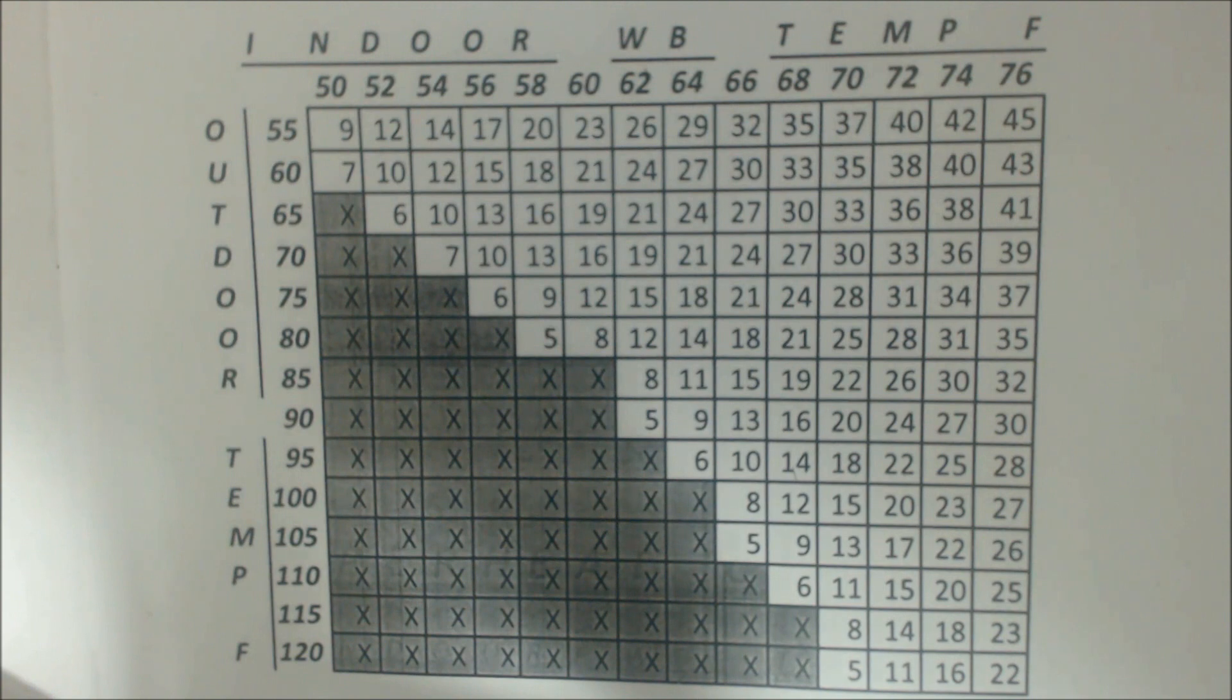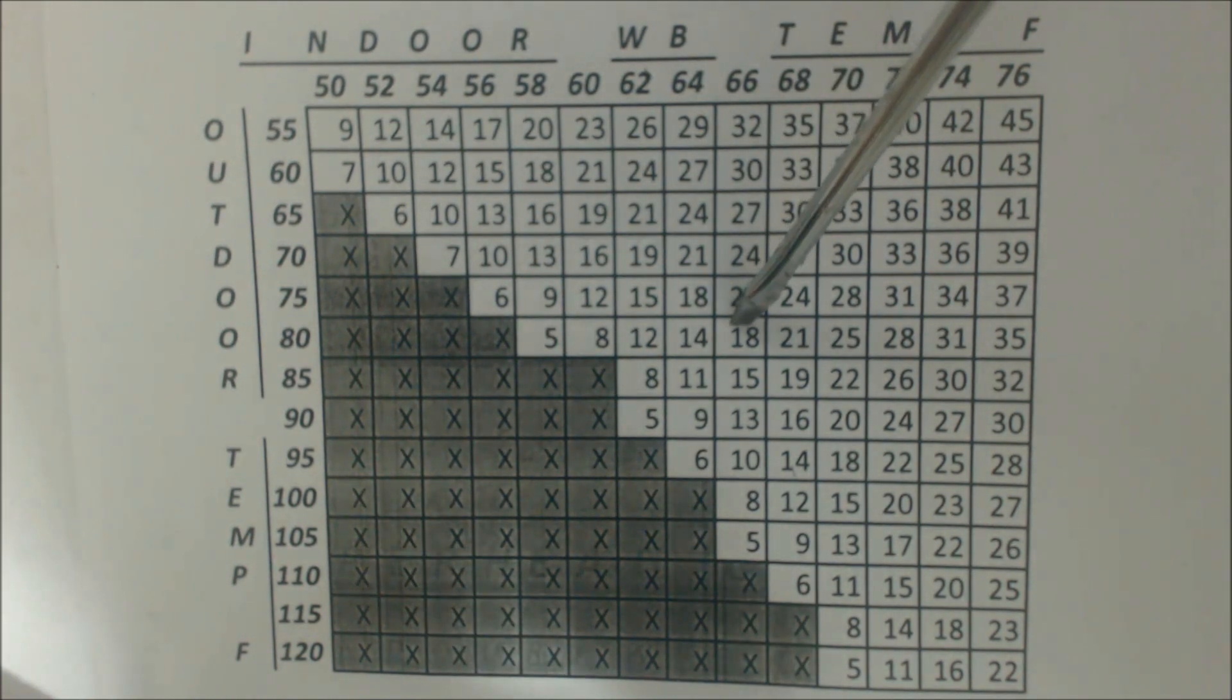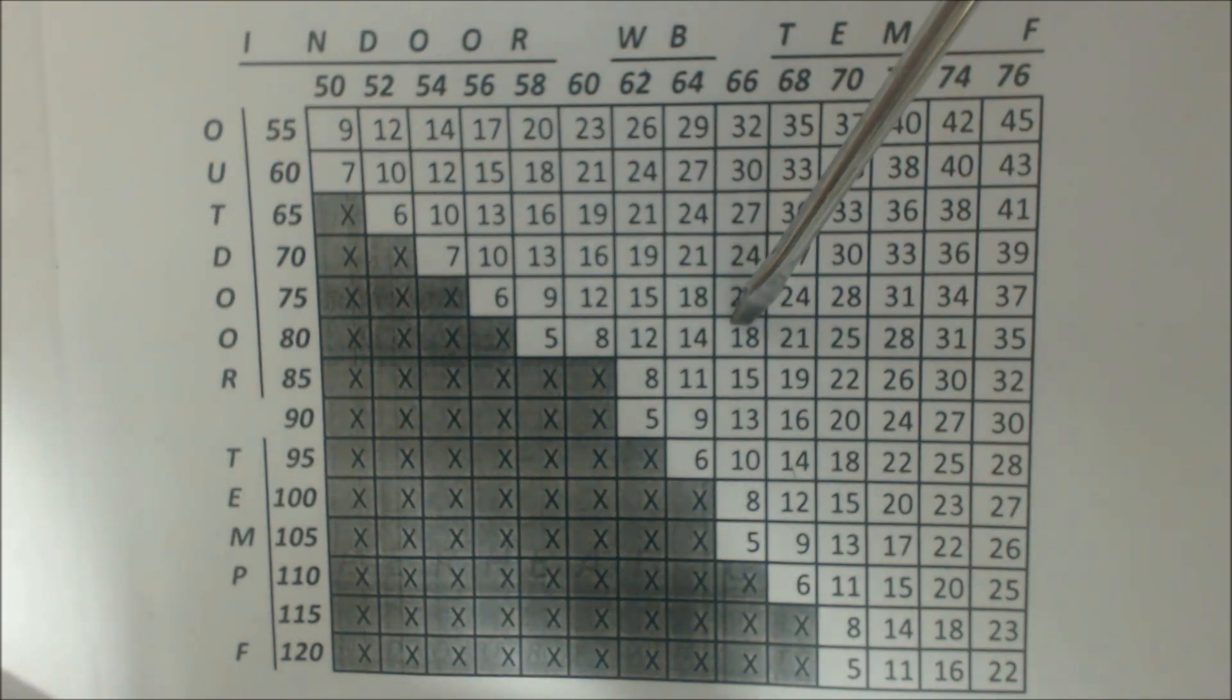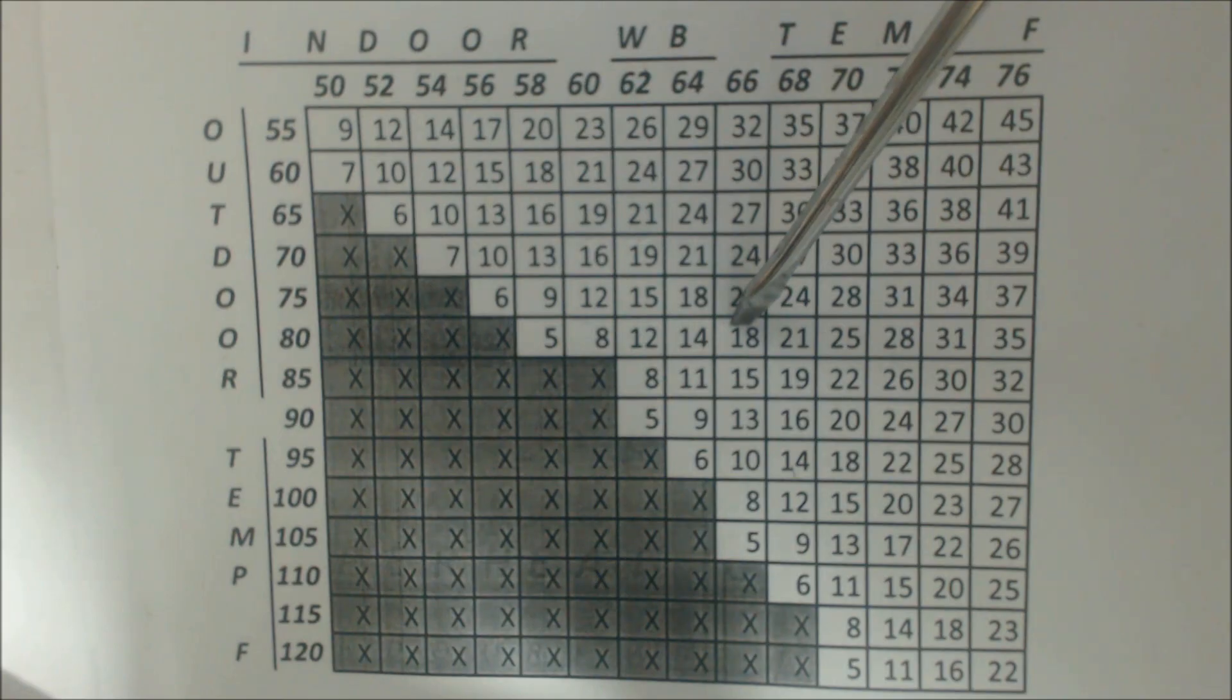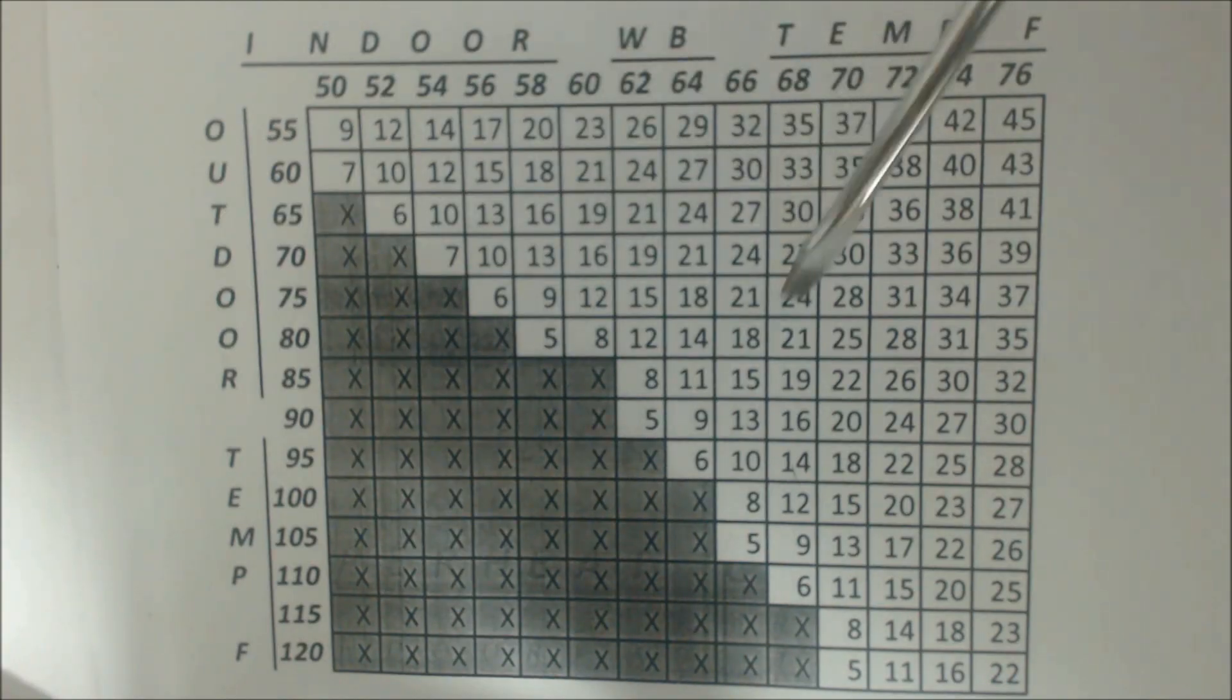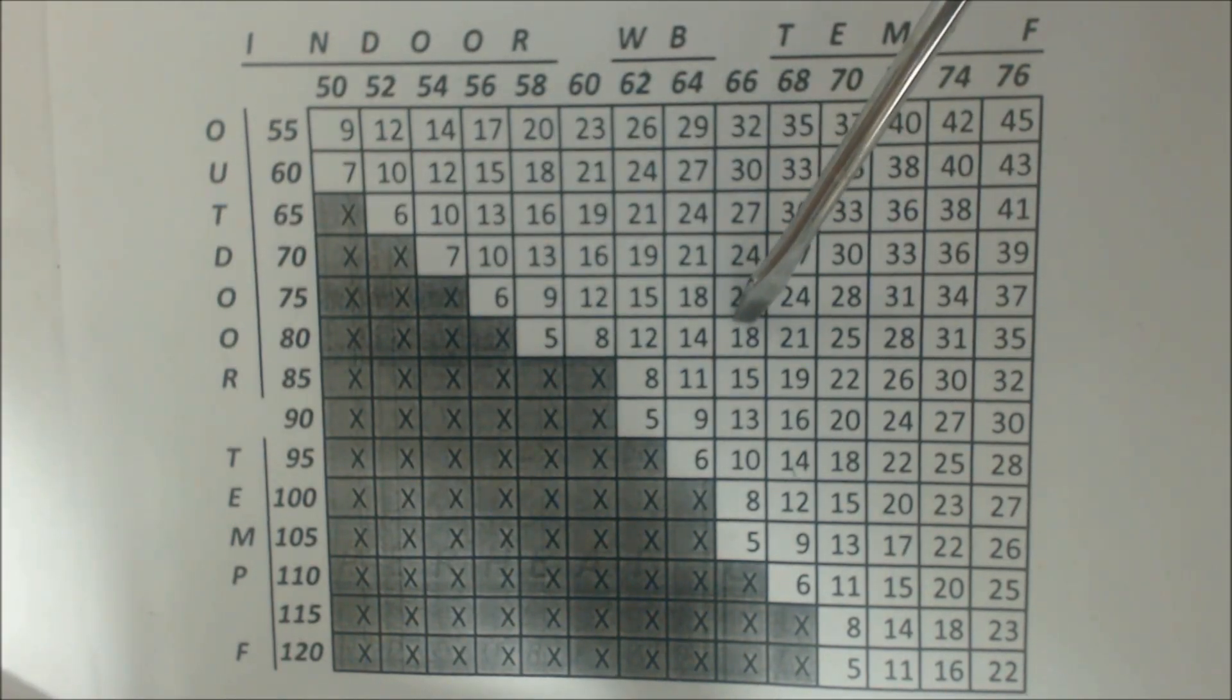With superheat, you just have a piston or maybe you have a capillary tube system. Usually when you walk up to the site, you're going to check to see if you have a TXV or if you don't have a TXV. If you don't have a TXV, you have some other type of metering device, either it's a piston or it's capillary tube. You use the superheat charging chart in order to charge that.